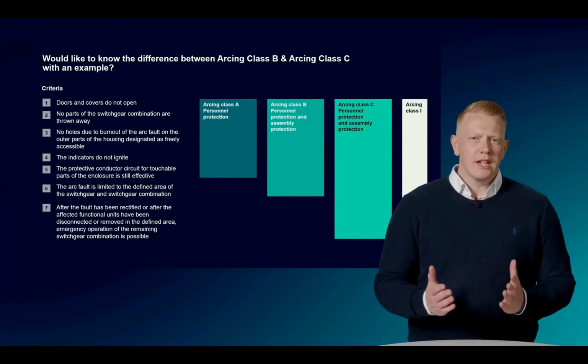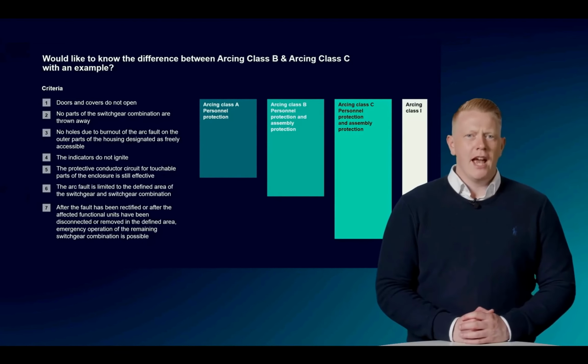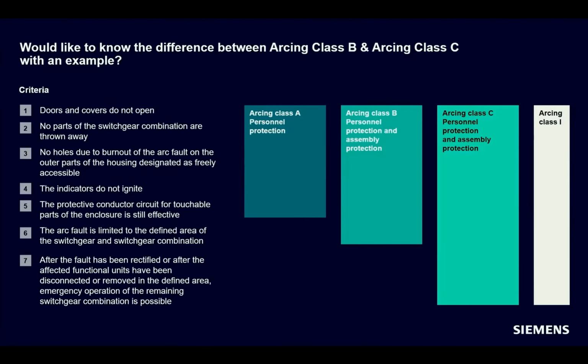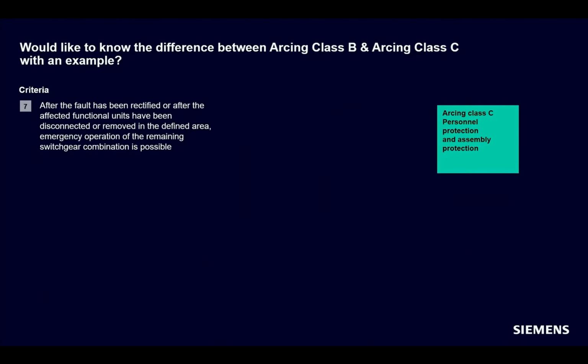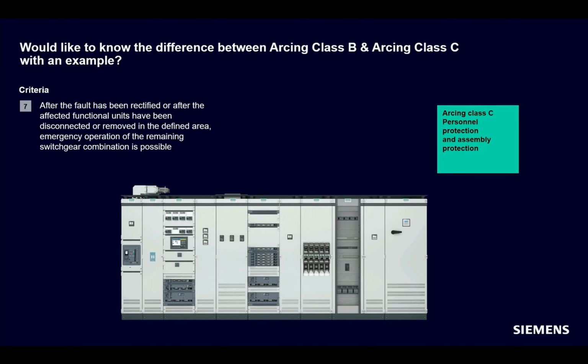Next question. I would like to know the difference between arcing class B and arcing class C with an example. The difference between class B and C is that class C provides so-called emergency operations after removing the affected part of the assembly. The assembly must be designed in a way that an affected part can be removed. So the design must be in some way modular. For example, withdrawable design where the affected unit would be removed and the rest is still working. Or an ACB section that, if affected, would be removed from the assembly.